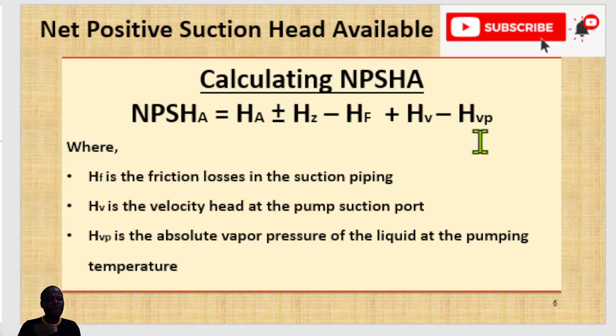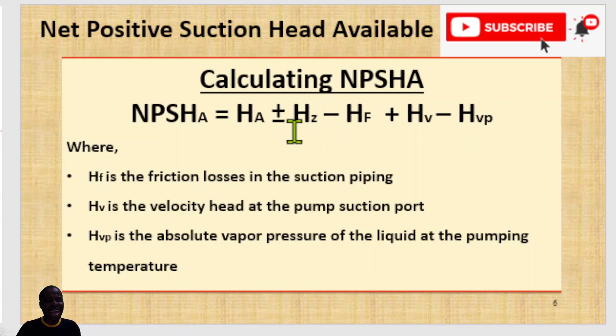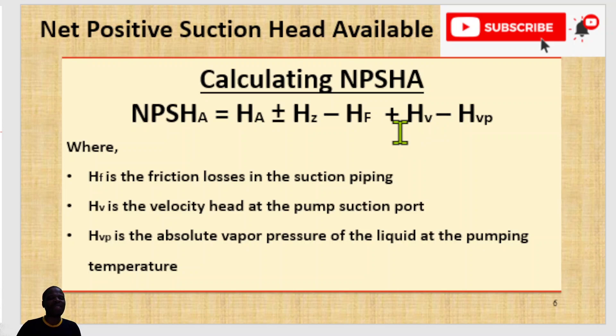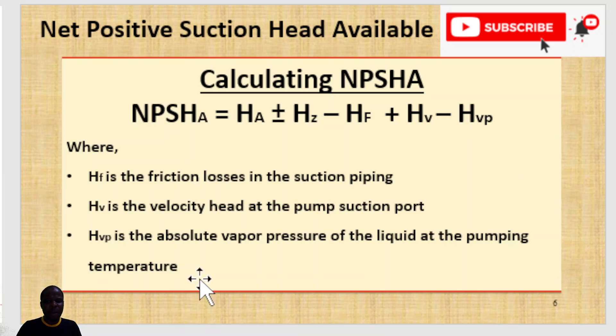When calculating your NPSHA, take note of the units — all parameters, including absolute pressure, static head, frictional head losses, velocity head at the pump suction port, and vapor pressure, must all be expressed in meters. This gives you the NPSHA, which is the net positive suction head available — the energy available at your pump suction to prevent cavitation.